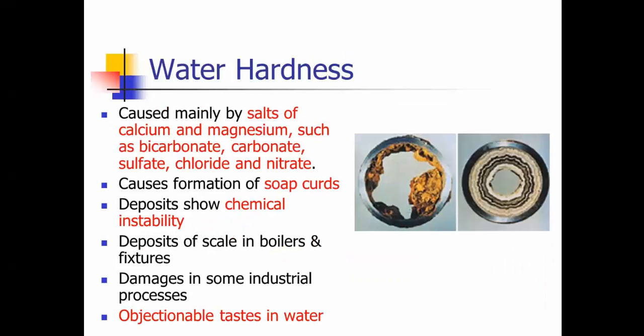Water hardness is caused mainly by salts of calcium and magnesium. You can see these two cutaways of pipe with the scaling on the inside. They cause formation of soap curds. They also show chemical instability of the water. And they scale, you'll get the scale in boilers and fixtures. They can also affect industrial processes. They also have objectionable taste and odor in the water.